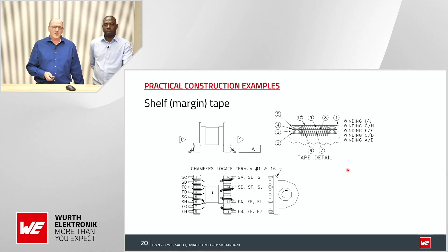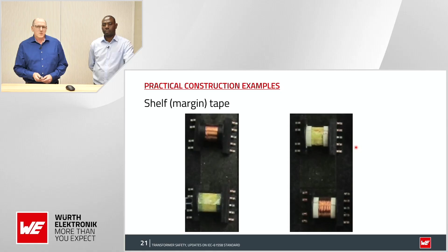In these pictures you can see this coil former in real design. You can see here the barrier left and right side directly designed in the coil former, and in the middle you can see the windings. On top we normally bring 1 or 2 layers of tape to realize the separation to the other windings, and on top you can see we have to bring the shelf tape left and right side with a special tape to realize the distance in the next layer, and then we wind the winding directly in the middle of the reduced chamber.